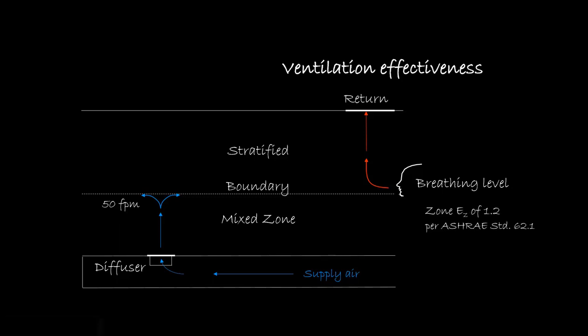ASHRAE Standard 62.1 recognizes this enhanced contaminant removal by awarding a ventilation effectiveness factor of 1.2 to UFAD systems whose projection to 50 feet per minute does not exceed 4.5 feet. The same is awarded to thermal displacement ventilation systems. Projection beyond this level captures contaminants within the occupied zone and thus is assigned an effectiveness factor of 1.0, that which is also awarded to overhead cooling systems.